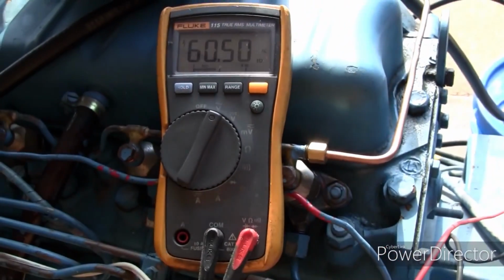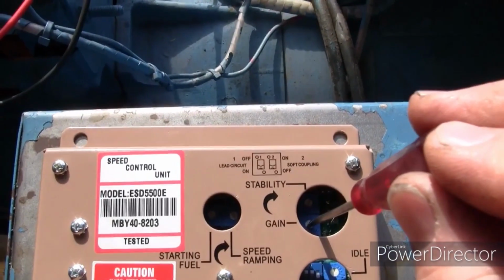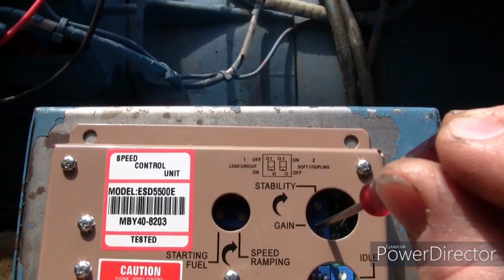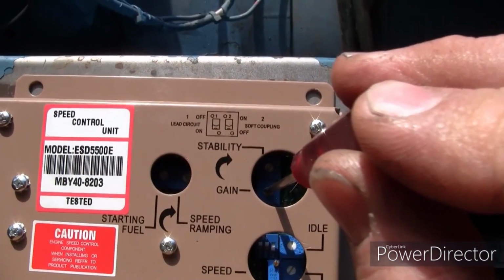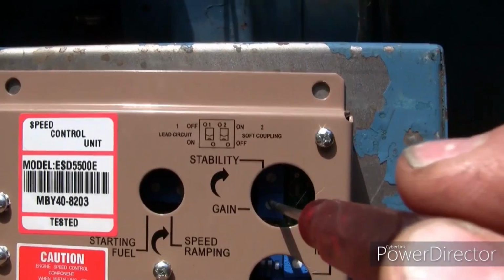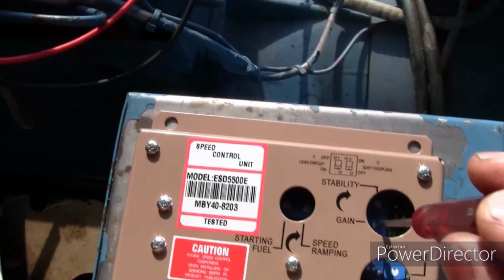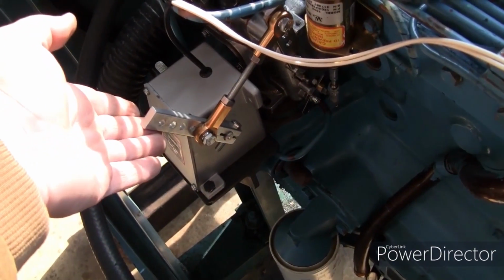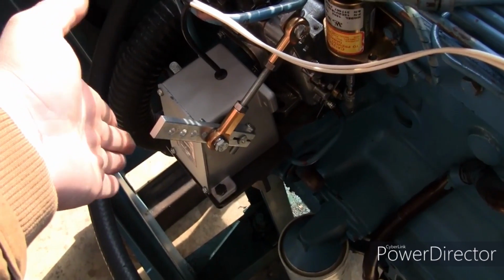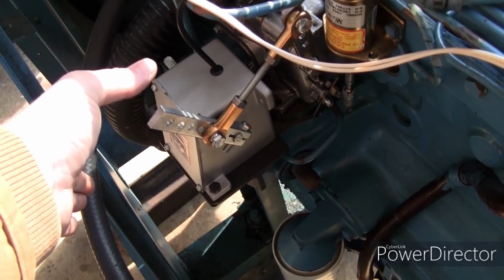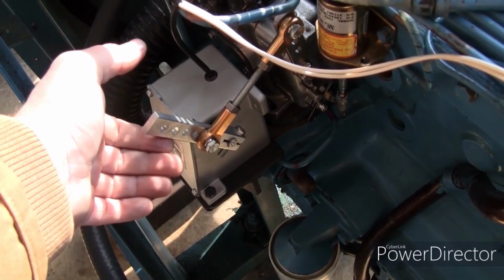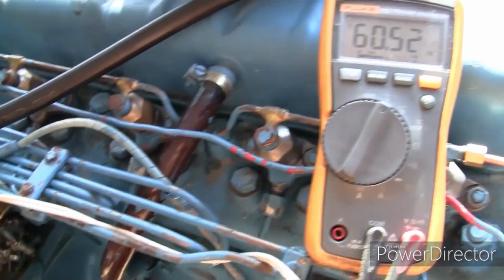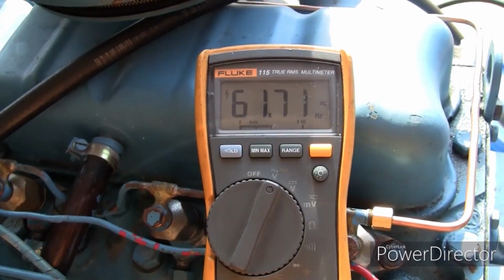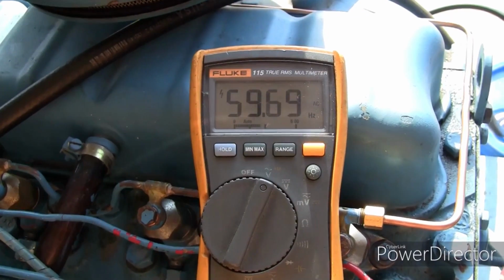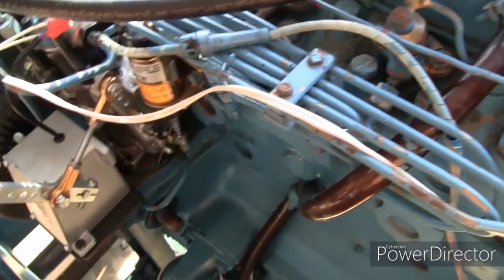The gain is going to control how rapidly the controller reacts to a change in speed. So just bringing it up slowly. Alright, let's see what we got now. Alright, you see how much more rapidly that lever shoots up? So I'm pushing it to minimum position, and then it shoots right back up. Now it overshoots quite a bit, but now we're still at 60.5 hertz here. That overshoot we'll compensate for with stability.